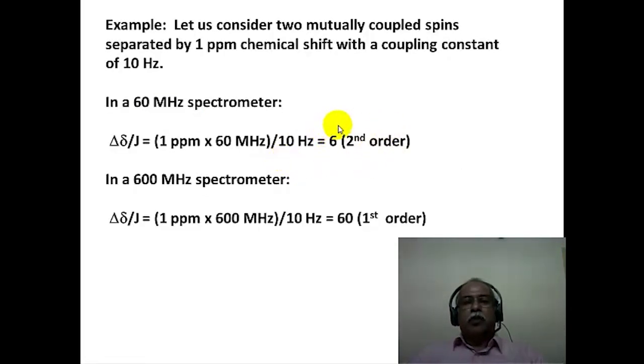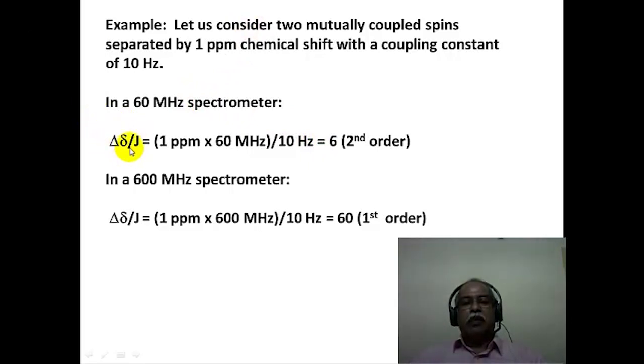Consider a simple example of two mutually coupled spins separated by about 1 ppm with a coupling constant of 10 Hz. In a 60 MHz spectrometer, delta-delta is about 60 Hz, giving a ratio of 6 — typical second order behavior. However, in a 600 MHz spectrometer, delta-delta becomes 600 Hz; divided by 10, the ratio is 60, placing the spectrum firmly within the first order domain.